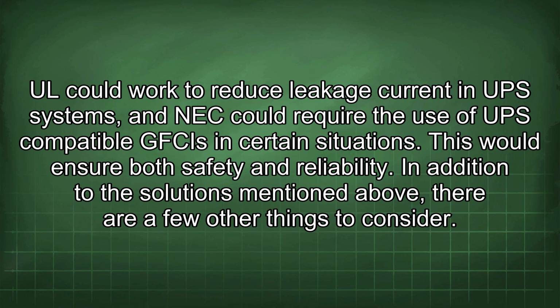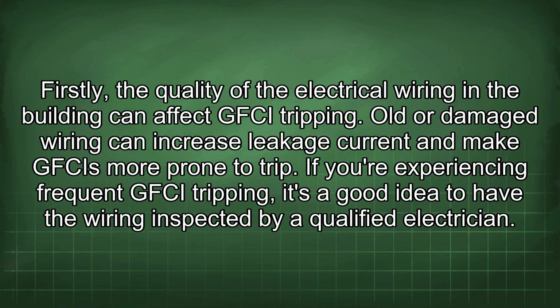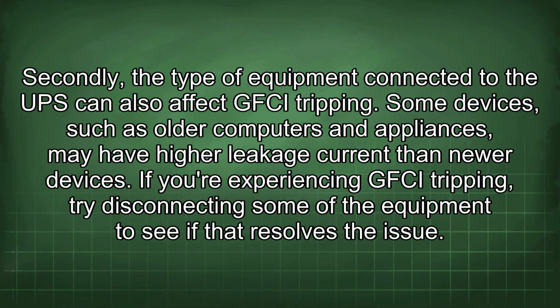In addition to the solutions mentioned above, there are a few other things to consider. Firstly, the quality of the electrical wiring in the building can affect GFCI tripping. Old or damaged wiring can increase leakage currents and make GFCIs more prone to trip. If you're experiencing frequent GFCI tripping, it's a good idea to have the wiring inspected by a qualified electrician. Secondly, the type of equipment connected to the UPS can also affect GFCI tripping. Some devices, such as older computers and appliances, may have higher leakage current than newer devices. If you're experiencing GFCI tripping, try disconnecting some of the equipment to see if that resolves the issue.